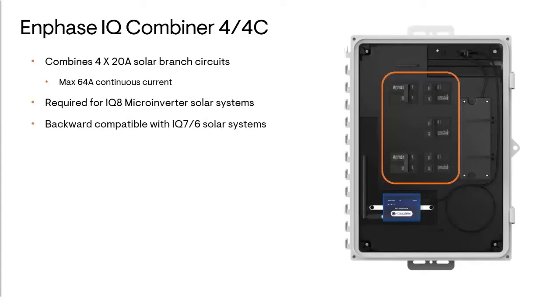The Combiner 4 or 4C must be used with IQ8 solar systems in backup power configurations. And the reason is that you can install hold-down breakers for all 4 breaker locations. Since the IQ8 is a grid-forming microinverter and could potentially still energize circuits during a power outage, even if the breaker is turned off, it has to have hold-down breakers.